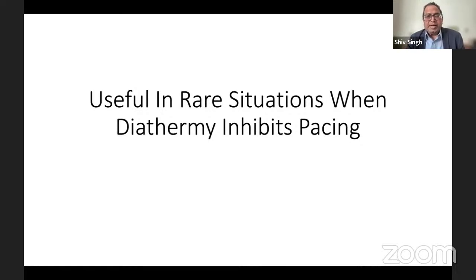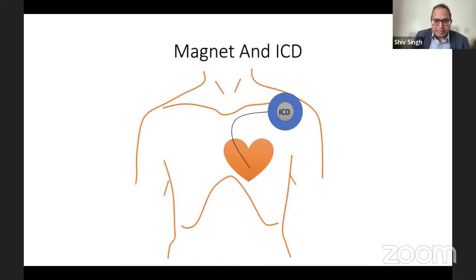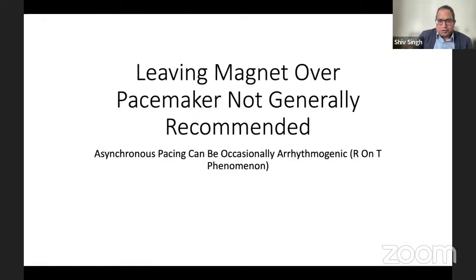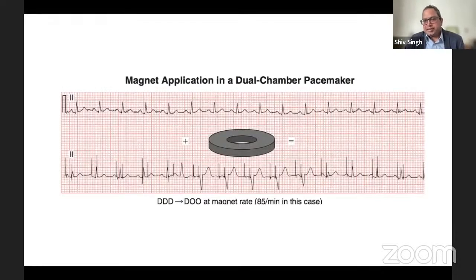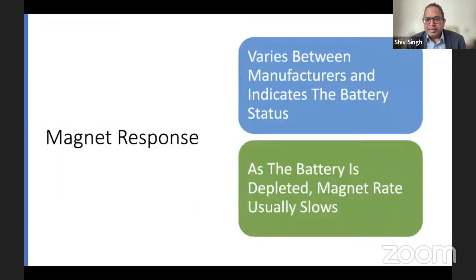So where do you actually apply the magnet? It's recommended that you should hopefully not need to have the magnet applied on the pacemaker unit permanently, because it sets in asynchronous mode, which can be arrhythmogenic as well. You can still have R-on-T phenomenon. And like I said, magnets are used to look at the battery status. As the battery gets depleted, the fixed rate will go down.